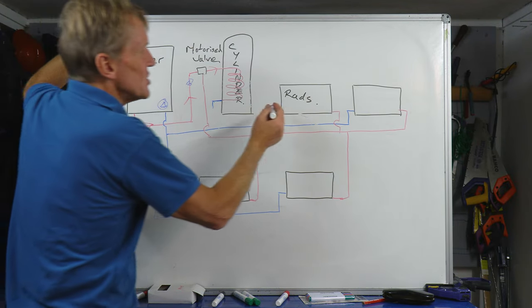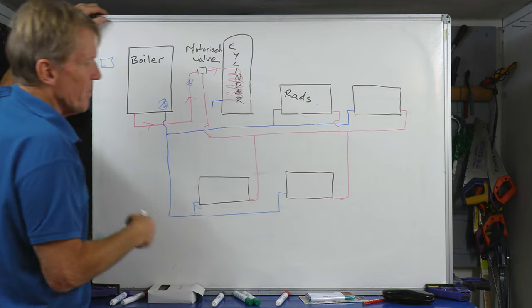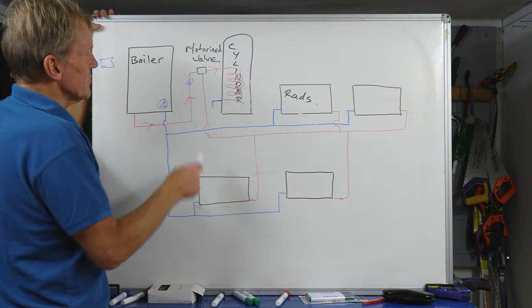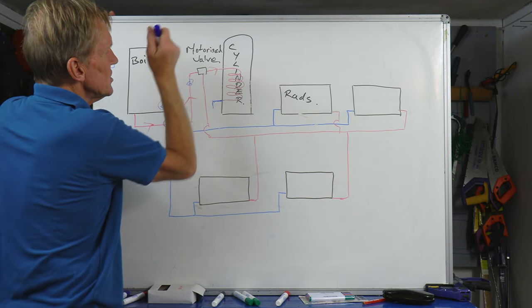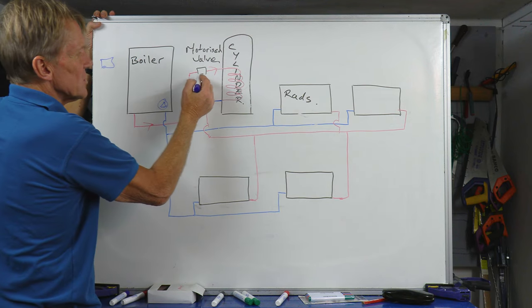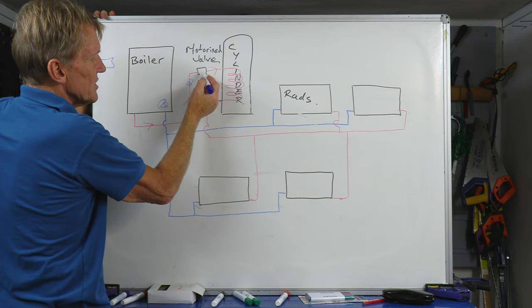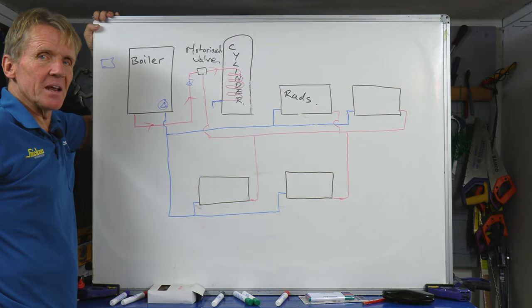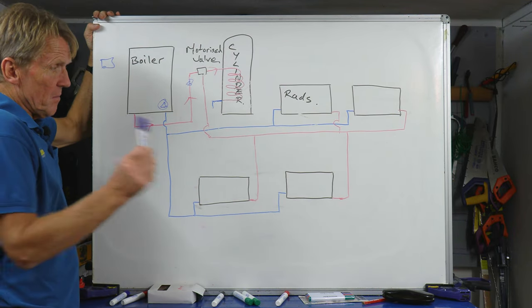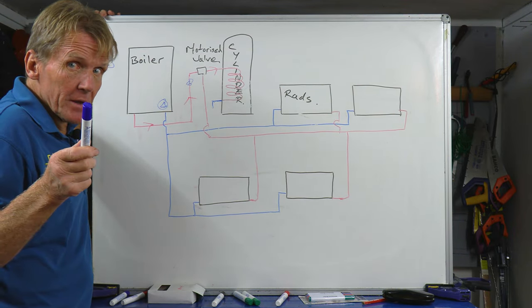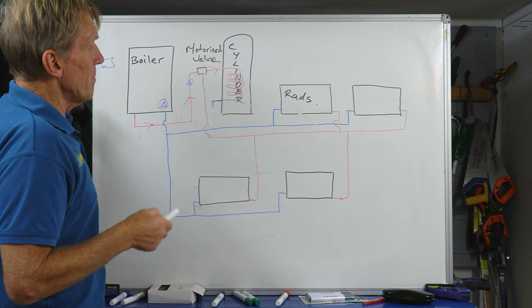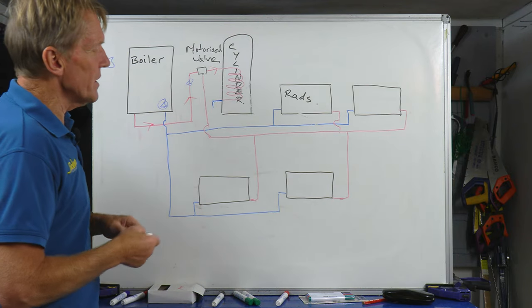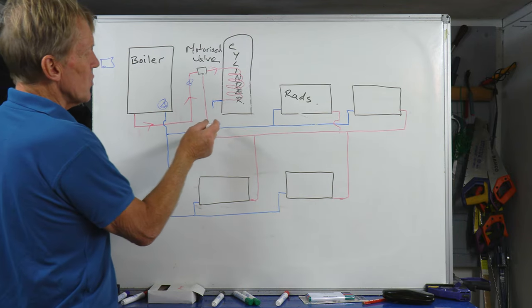And then you find that when the hot water is running, these radiators are warming up. They may not be getting fully hot, they may just be warming up a little bit, but they're warming up. So the plumber comes along as I said and he changes the motorized valve because he said that's the culprit. What's happening is it's creeping by there, it's going through the radiators and it's warming them up. And that may be happening, that can happen, but a lot more likely, and the thing that they should actually be proving, is that we've got something called reverse circulation.